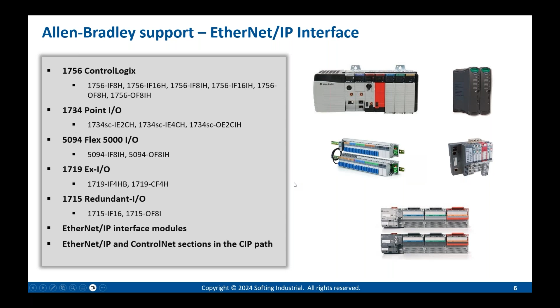Now, as promised, I will show you the solution architecture, how it would look like in a plant. You have your HART devices connected to an Allen Bradley remote IO, and through Ethernet you make the communication with the PLC. Sometimes you have the possibility to connect the HART devices directly to the Allen Bradley PLC. So both ways work, depending on the PLC and remote IO situation - HART devices could be connected directly to the PLC, or you can connect them via the remote IO.